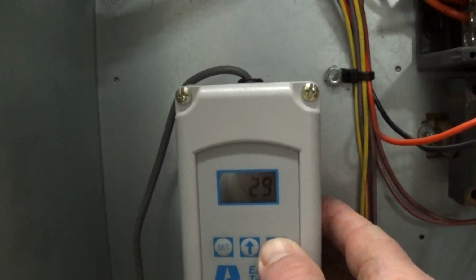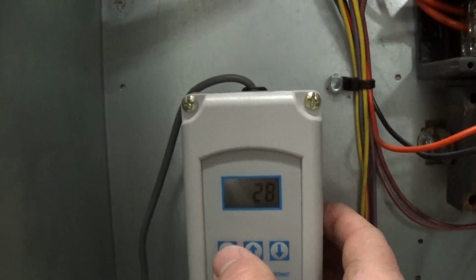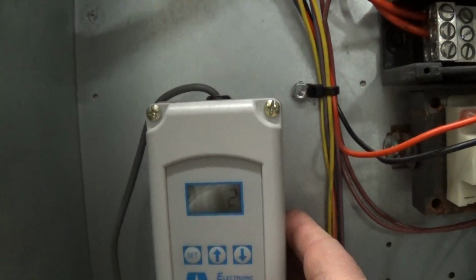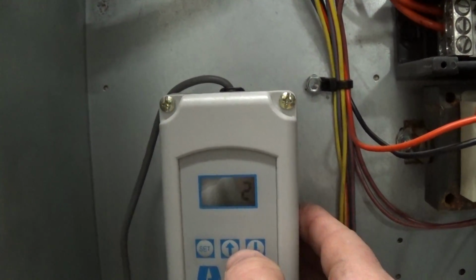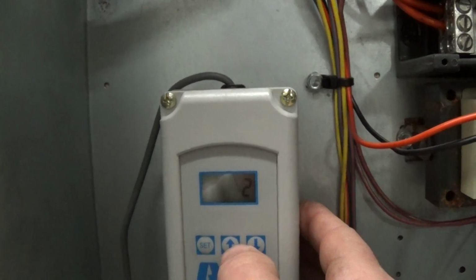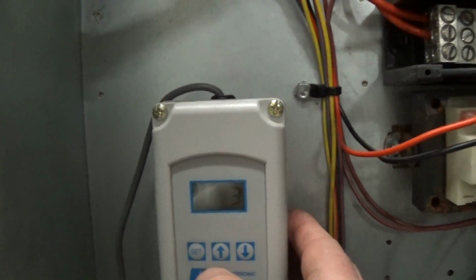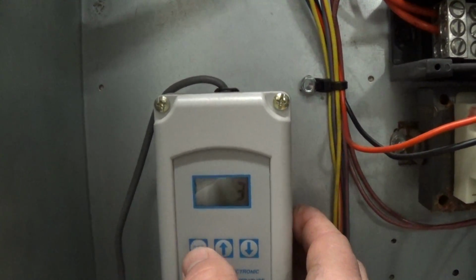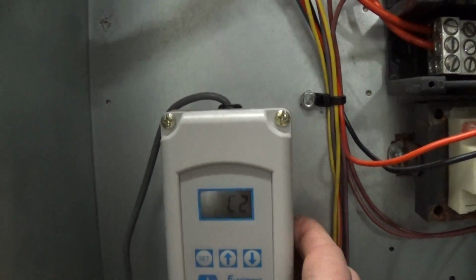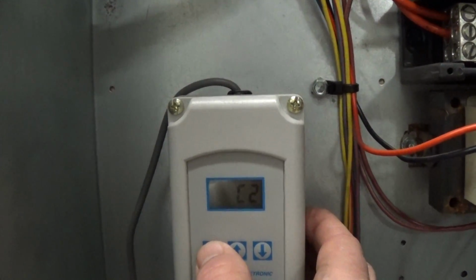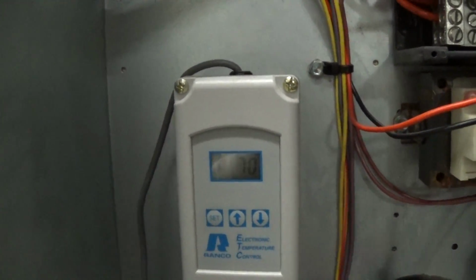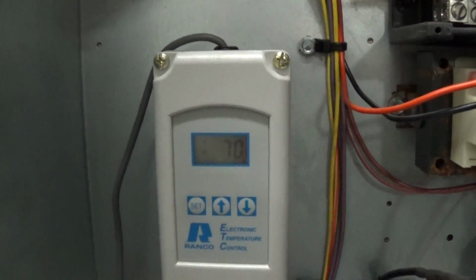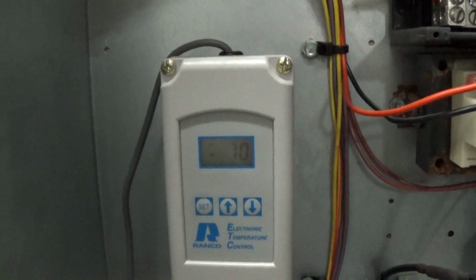Now the right thing to do, when you have 2 compressors, is have the set point the same, but have the differential a little bit higher on the second one, and you can alternate back and forth. I'm going to have the differential on this one at 3, okay? I'm going to press set again, cooling mode 2. Set again, it reverted back to what the process fluid water was, and you can hear both my compressors started.